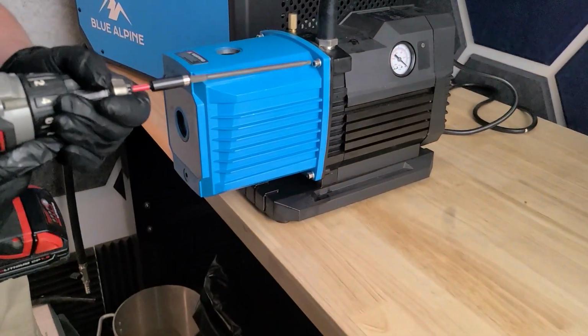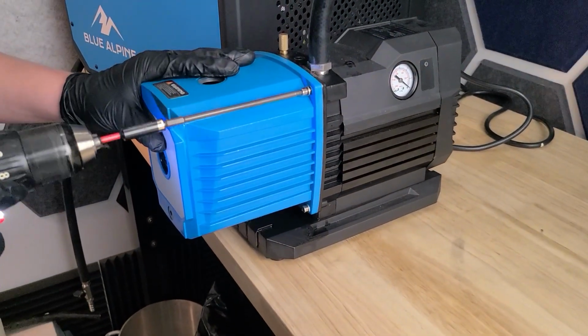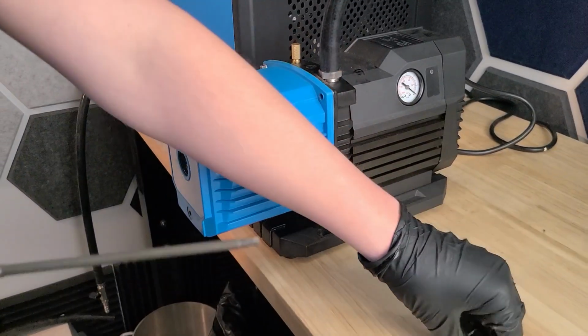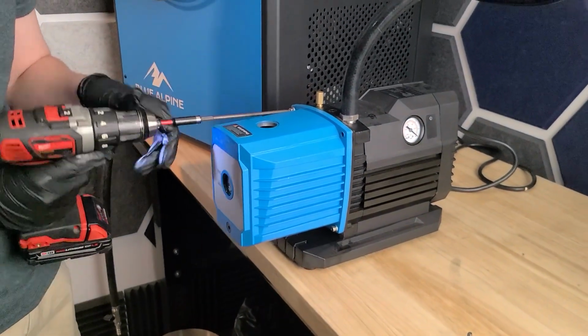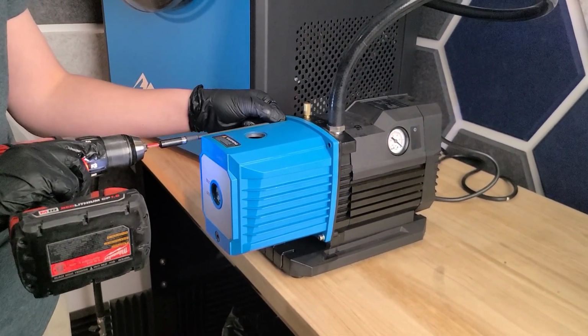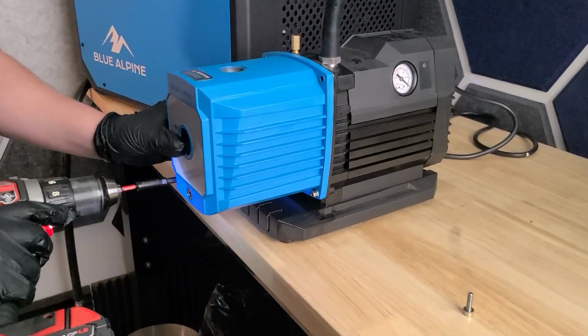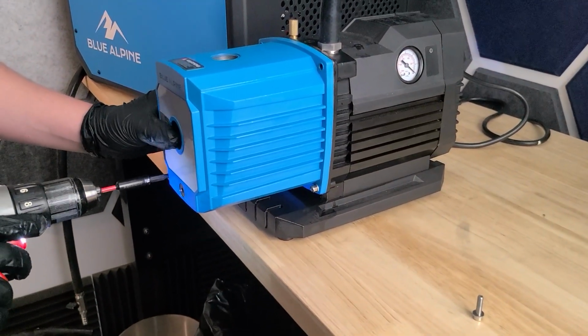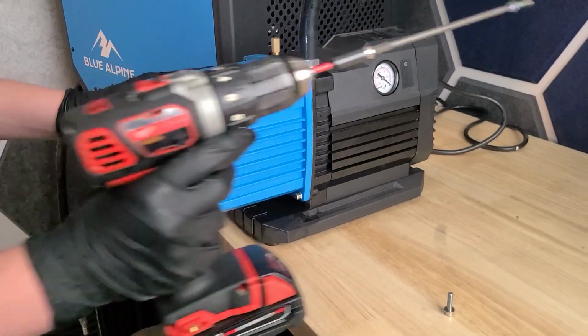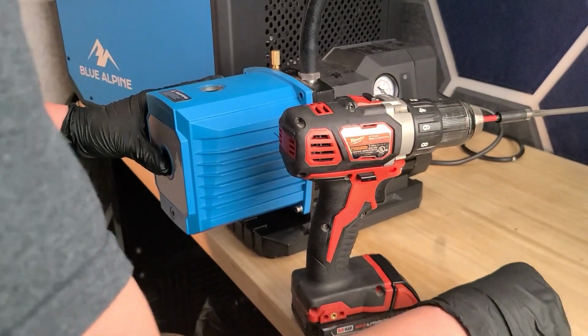The next step is going to be removing the 4 screws that hold on the pump head. Be careful when you take out the 4 screws, put them somewhere where they're not going to get lost. It is really hard to keep track of these screws sometimes, so please just be cautious on where you're putting them. And taking off these 4 screws, you are going to want to hold tension on the head so that when you take the last screw out, the head doesn't go falling on the floor. There is nothing holding up the head after you take the 4 screws out.